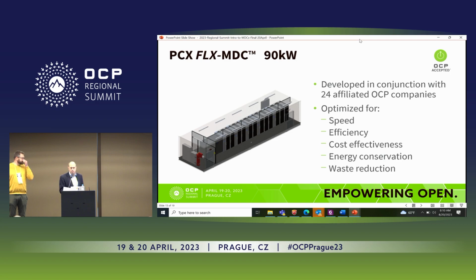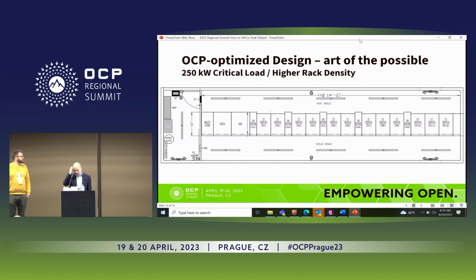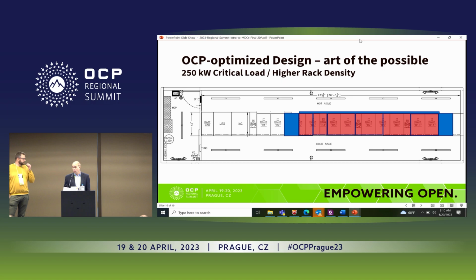It's got 12 racks and a UPS, and I started thinking about what if you OCPized this thing. The first thing that struck me was I can reduce the number of cabinets from 12 to 10, drive a higher density, and take this 90 kW up to about a quarter megawatt. All I have to do is get rid of the in-row coolers, add rack heat exchangers with a couple of cooling units, a couple of cooling distribution units, and a couple of cooling units on the end to handle whatever environmental load and other heat sources besides the IT. I add a small area for power distribution, and that's my data center now.